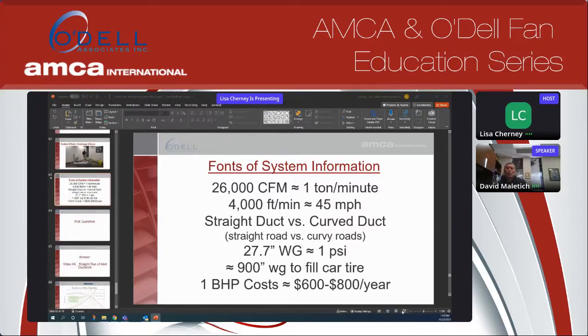And the last one is that if you're running a fan 24/7 or any device 24/7, depending on what your utility rates are, it's going to cost you about $600 a year to consume 1 brake horsepower that's constantly running. So if you can save 10 horsepower on a system, you're going to save $6,000 a year running that fan or any device on that system.